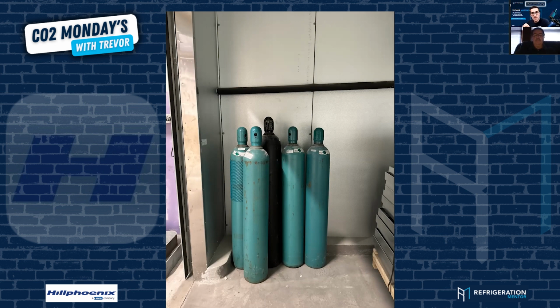The problem is when you start going too low of the quality of CO2, and I did so much investigating on this, is that you can get other non-condensables in there. So not moisture, but you can have some oxygen, you can have nitrogen. Yes. That's the problem when you start to go with lower and lower quality CO2. And always be careful, especially if you're starting your first new CO2 rack and your local distributor doesn't usually carry CO2. Make sure you're not getting helium capped tanks. Yeah, exactly. All right.